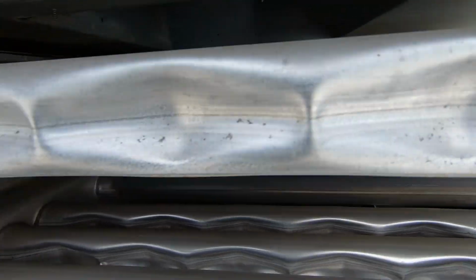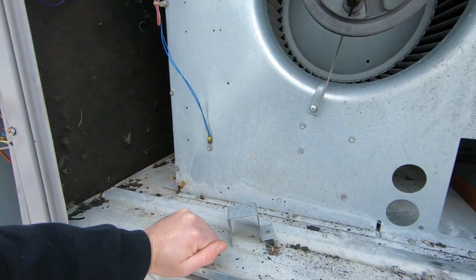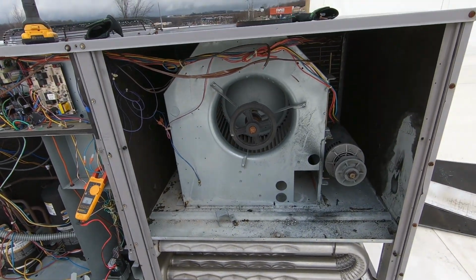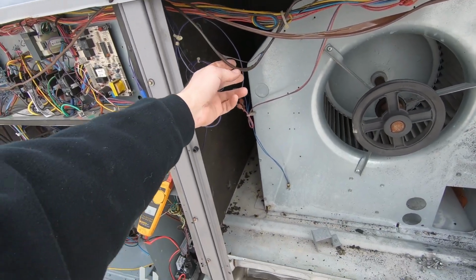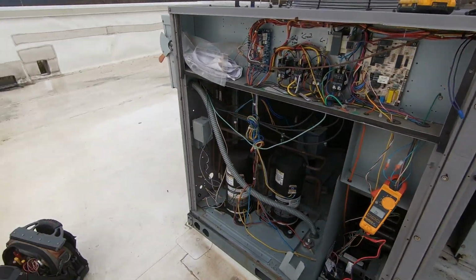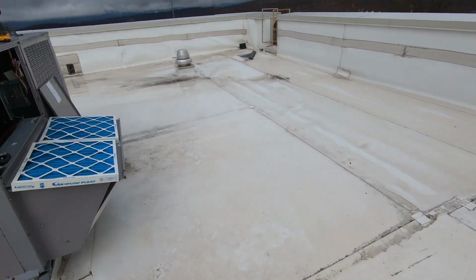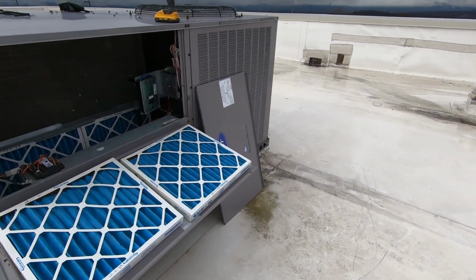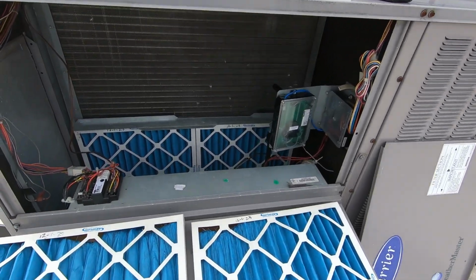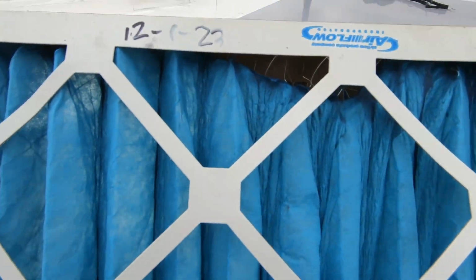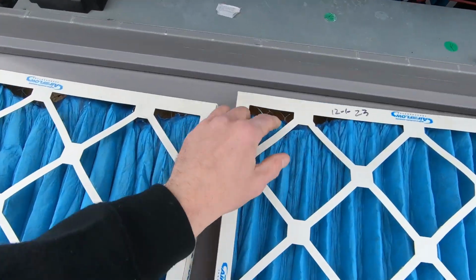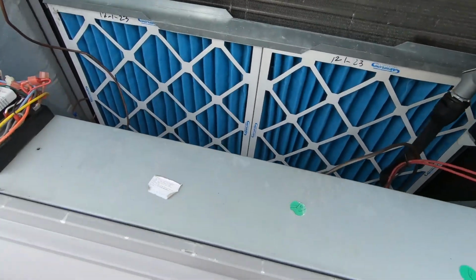operating. I do want to give this heat exchanger another good look, because just off the fact that these wires way up here are melted, it had to have been incredibly hot. Oh, you're gonna love this. So I'm pulling the filter so I can gather the filter and belt info so we can get it entered into our system. It got so hot, it melted the filter. Do you see that? That filter is melted all the way up at the top. This one and this one. Melted. I've never seen melted filters.